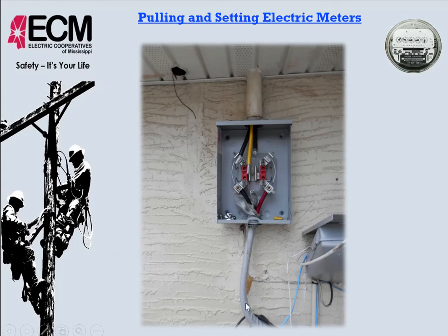Okay. Here's one here. This is called tray cable. It's an old way of doing things. This is not sufficient protection. This would need to be in conduit. So that's not a good idea. Also, I like the color-coded cables. This is a good way for us to identify our neutral. On the weatherhead, it being yellow, it'd be a singular color all the way from one end to the other. Kind of helps with that.